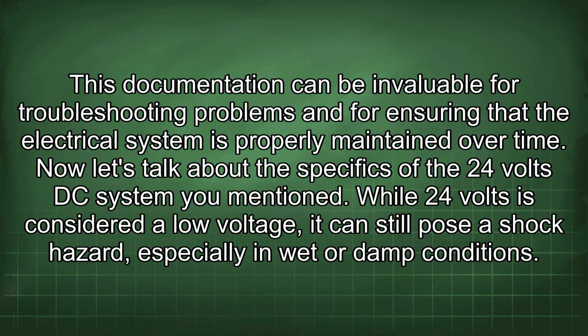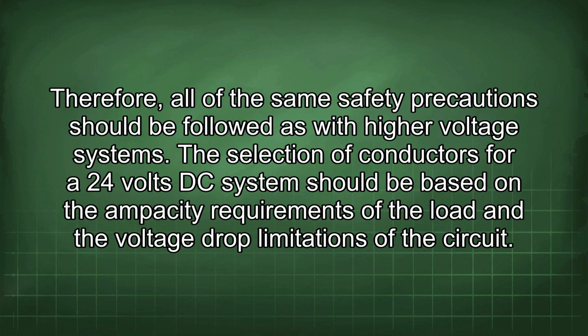Now let's talk about the specifics of the 24 volts DC system you mentioned. While 24 volts is considered a low voltage, it can still pose a shock hazard, especially in wet or damp conditions. Therefore, all of the same safety precautions should be followed as with higher voltage systems. The selection of conductors for a 24 volts DC system should be based on the ampacity requirements of the load and the voltage drop limitations of the circuit.